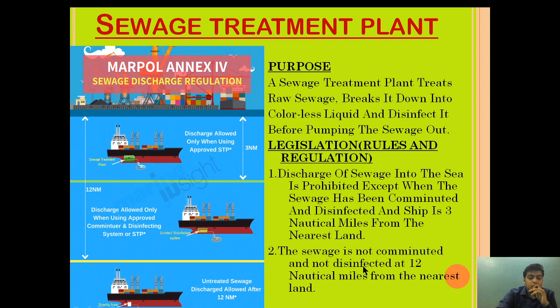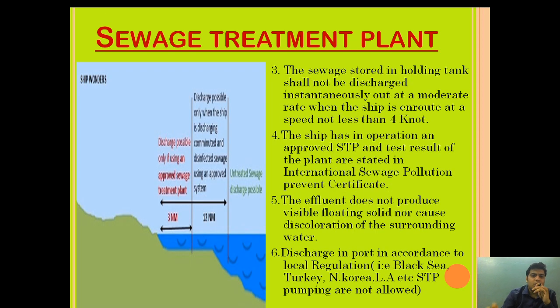If the sewage is not comminuted and not disinfected, we need to discharge it at 12 nautical miles away from the land. If we don't have a sewage treatment plant and only have a holding tank, sewage disposal is also allowed, but at 12 nautical miles away from land, at a moderate rate, when the sewage is not comminuted and not disinfected.